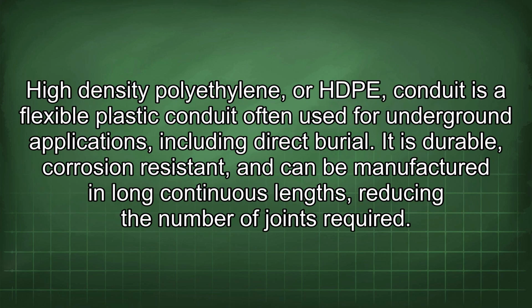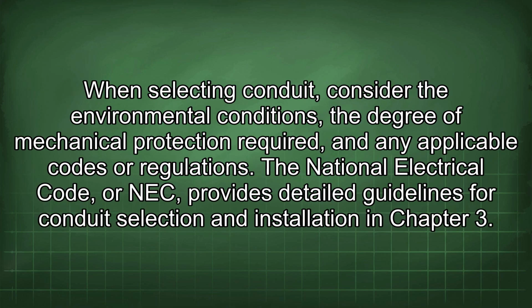High-density polyethylene, or HDPE, conduit is a flexible plastic conduit often used for underground applications, including direct burial. It is durable, corrosion-resistant, and can be manufactured in long continuous lengths, reducing the number of joints required. When selecting conduit, consider the environmental conditions, the degree of mechanical protection required, and any applicable codes or regulations.